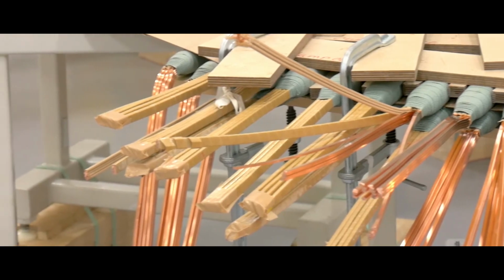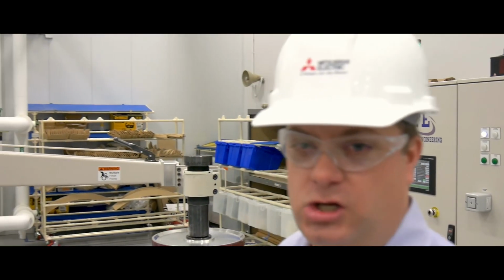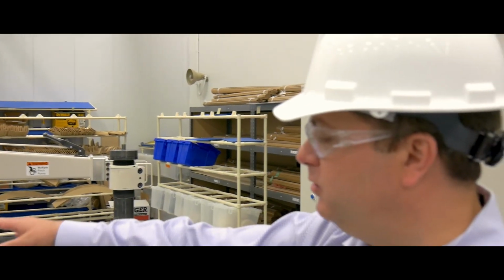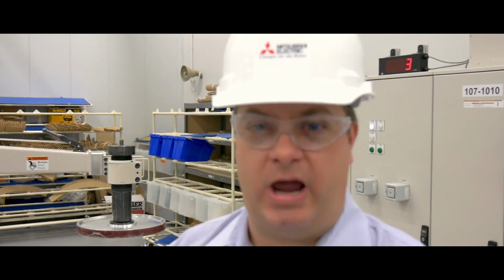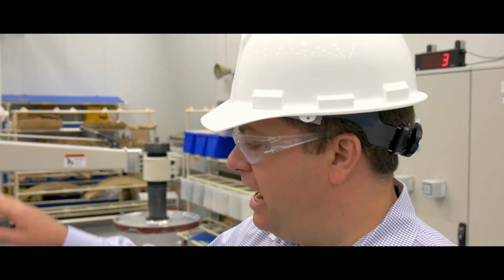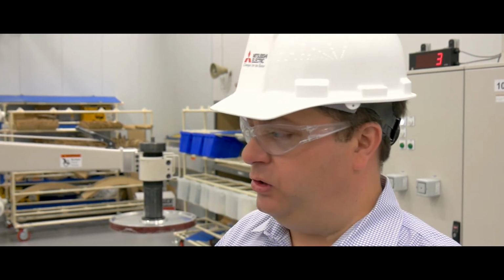Another unique feature of our windings is utilizing continuous conductor between adjacent coils. This minimizes the number of brazing connections in our windings, reducing them by about 50% by using continuous conductor between adjacent coils. That's another unique feature of our winding process here.